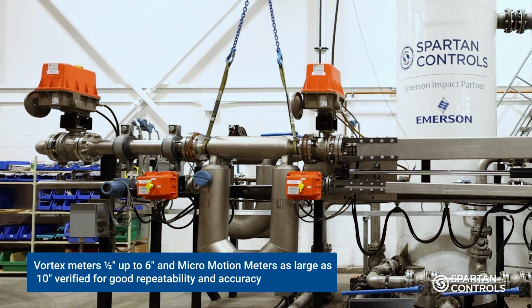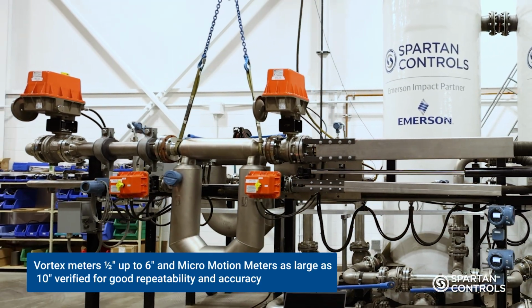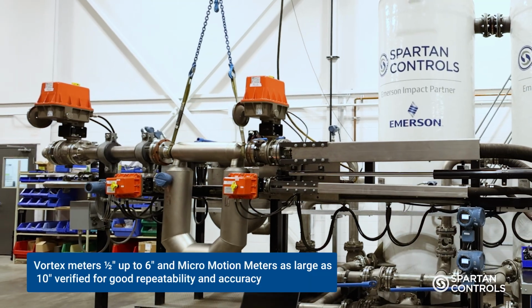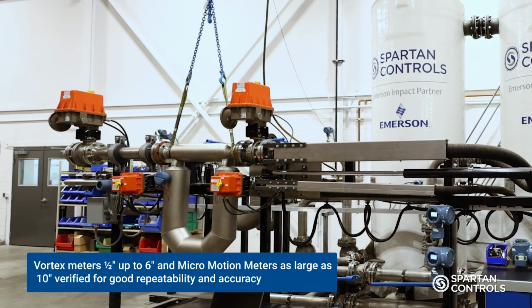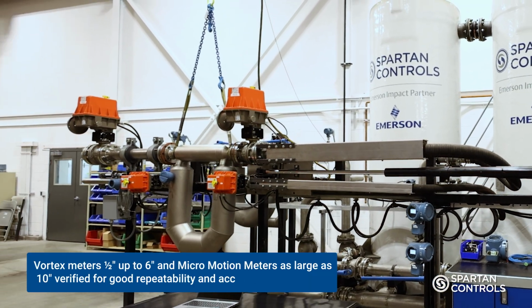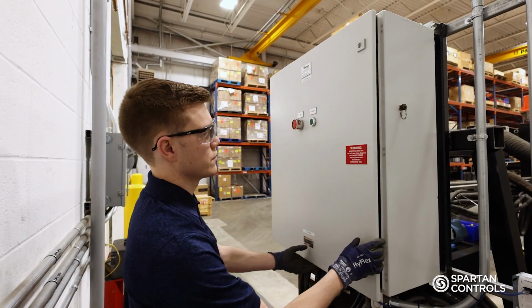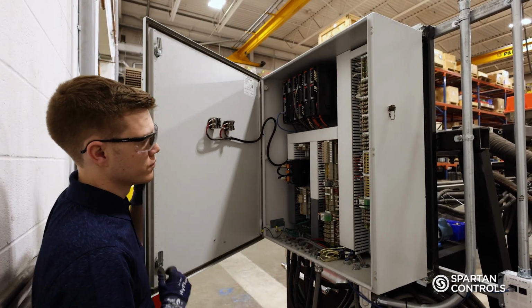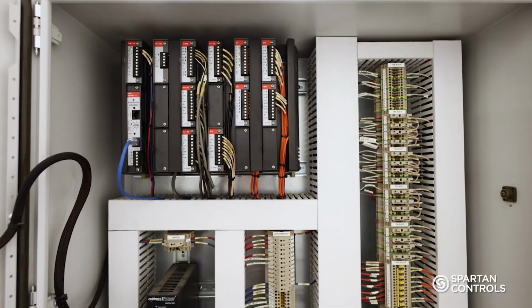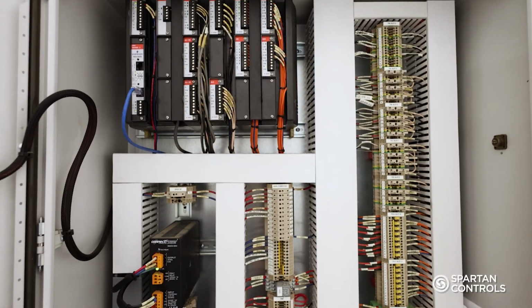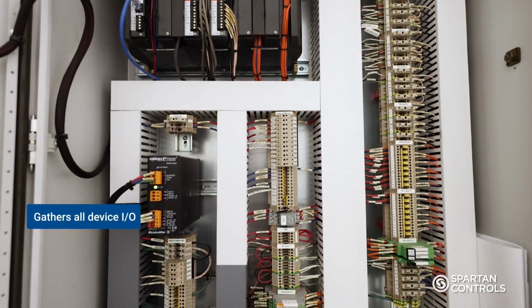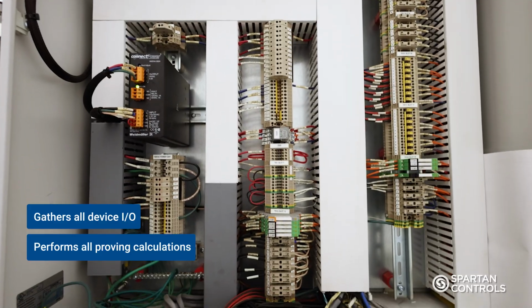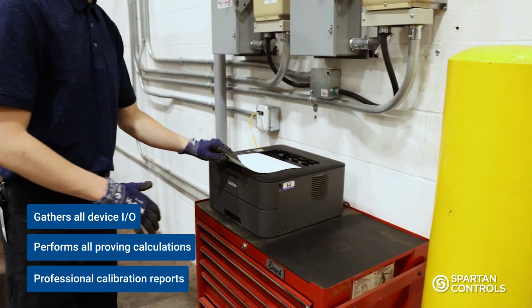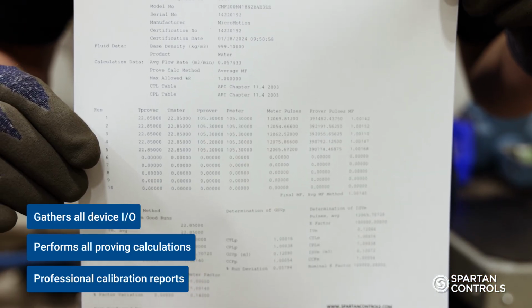All of these sizes and types of meters in the past would have been sent out of the country for calibration and verification. By utilizing a sophisticated ROC 800L proving flow computer, our master meter proving stand gathers all device I/O, performs all proving calculations, and creates professional calibration reports that are stored to a customer profile database.